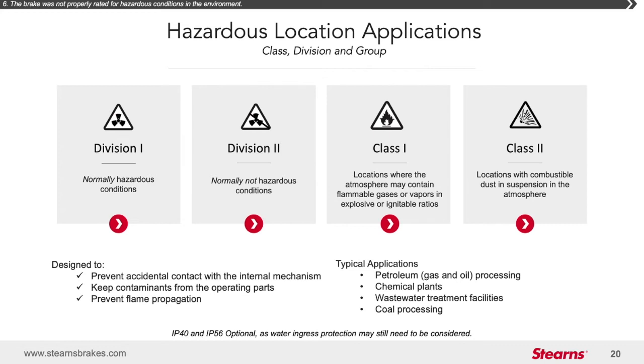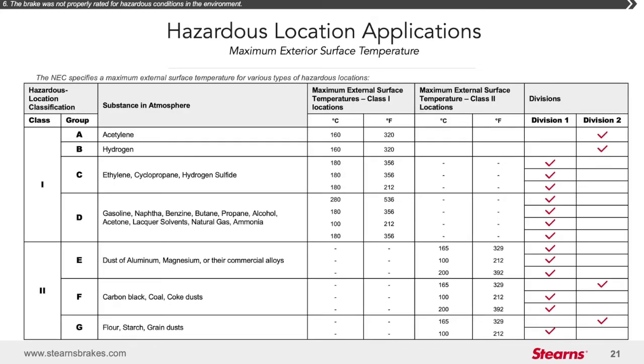The classes define the type of explosive or ignitable substances which are present in the atmosphere. Class 1 is locations that may contain flammable gases or vapors in explosive or ignitable concentrations. An electric disc brake for Class 1 locations is built to not allow flame or spark to rupture the enclosure.